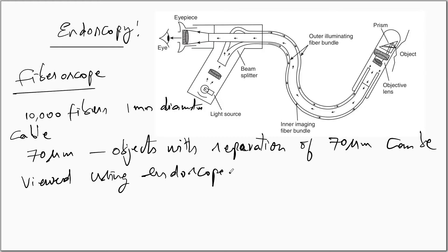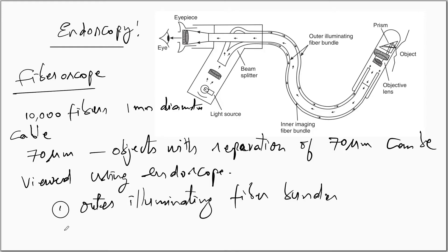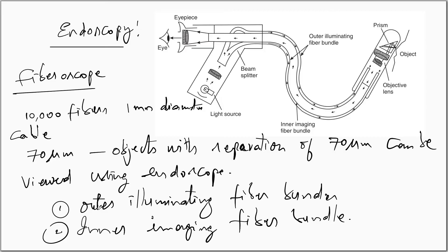The endoscope has two fiber bundles: the first is the outer illuminating fiber bundle, and the second is the inner imaging fiber bundle. Through the illuminating fiber bundle, we launch light into the inner parts of the body. A light source and certain optics are used to make the beam collimated and focused onto the outer illuminating fiber bundle. A beam splitter is used here, which splits the incident beam into equal or unequal parts depending on its structure, enabling light to be launched equally into all fibers of the outer illuminating fiber bundle.